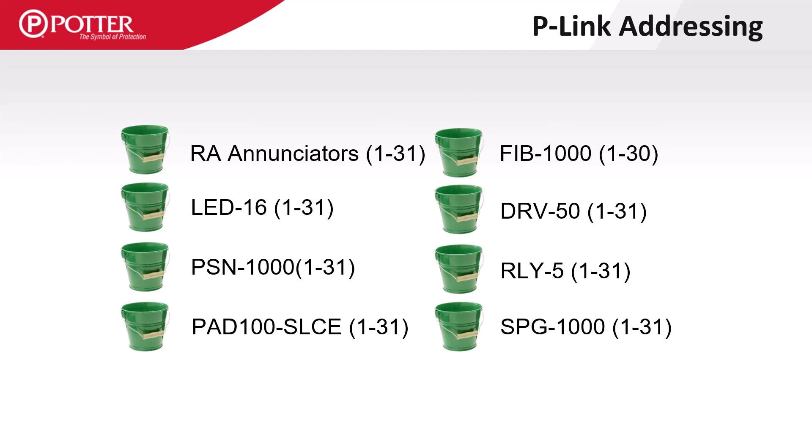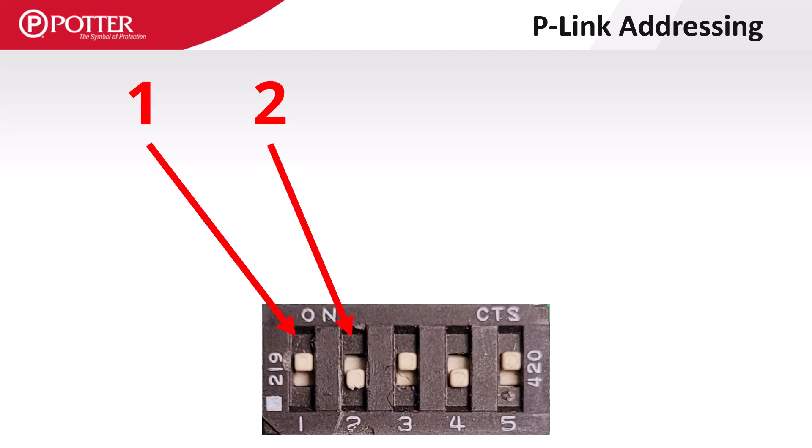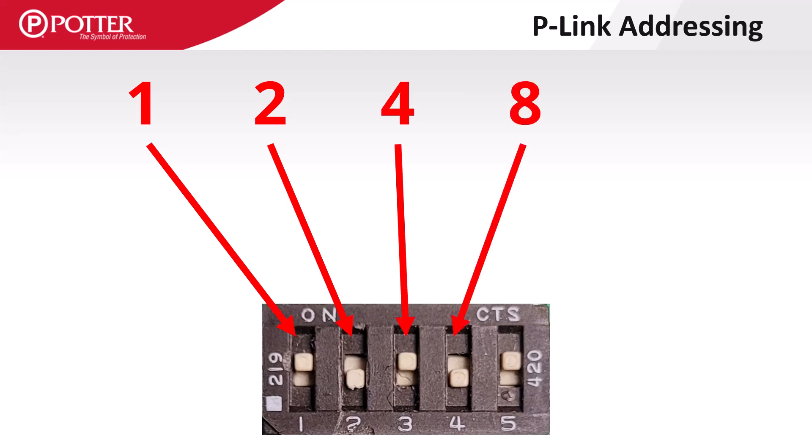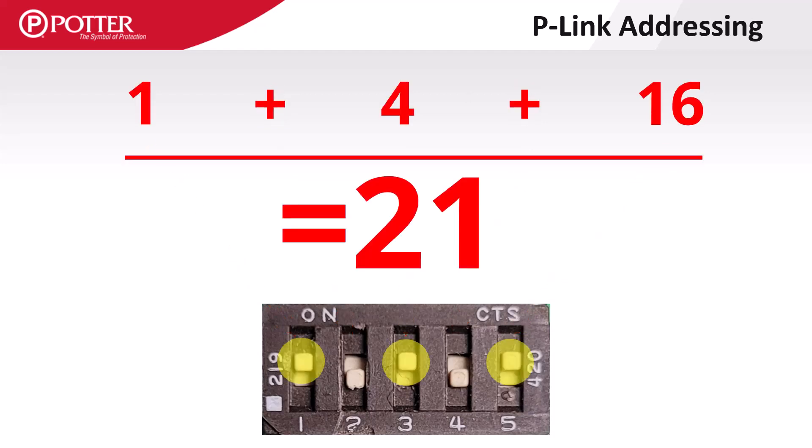Potter control panels can differentiate between P-Link device types, so a power supply, an SLC expansion card, and an annunciator can all be addressed 1. P-Link addressing is binary, meaning switch 1 equals 1, switch 2 equals 2, switch 3 equals 4, switch 4 equals 8, and switch 5 equals 16. To get address 21, turn on the 1, 3, and 5 dip switches.